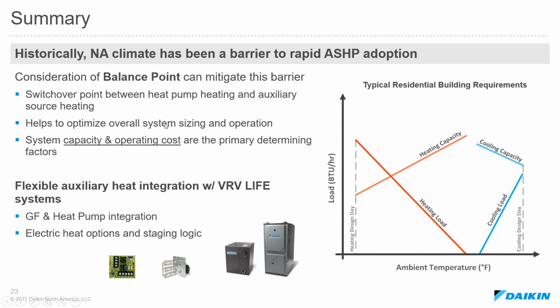So this introduces the concept of balance point. We talked about what balance point is. We talked about how VRV Xpress calculates it for us. We looked at a few examples. We looked at how to apply it to the outdoor unit. It's a field setting on the outdoor unit. And then we also looked at different aspects of it, capacity being the main one: what physically can the system do?